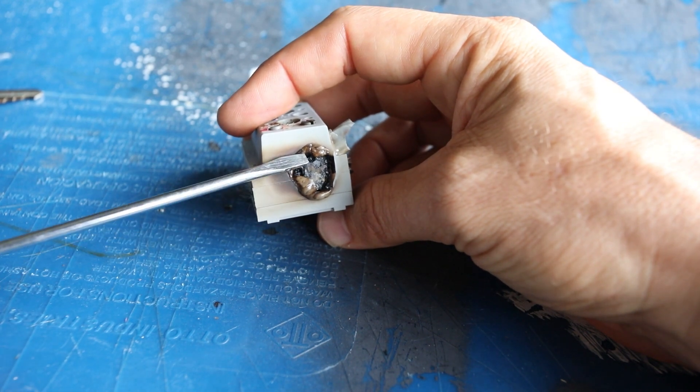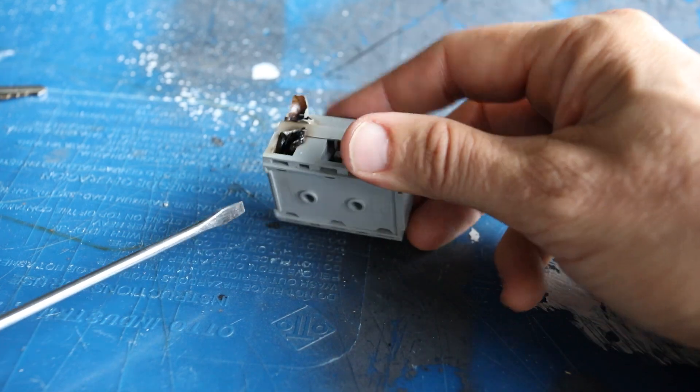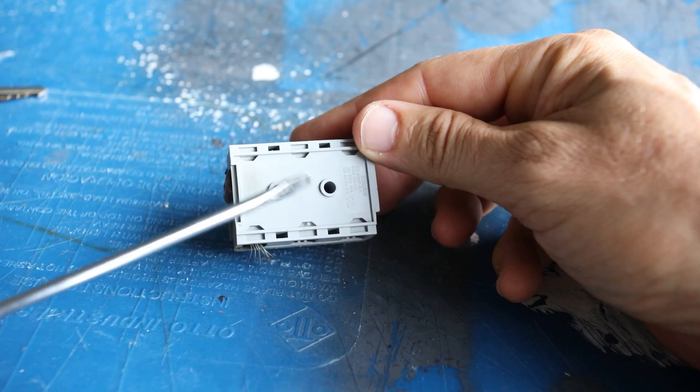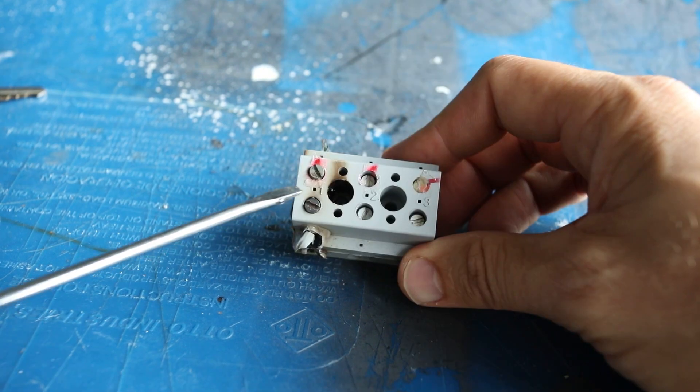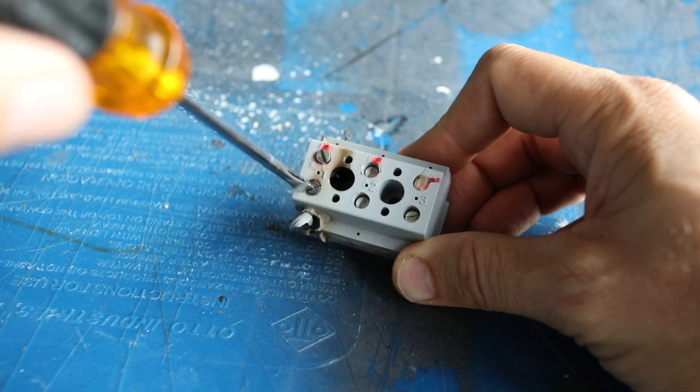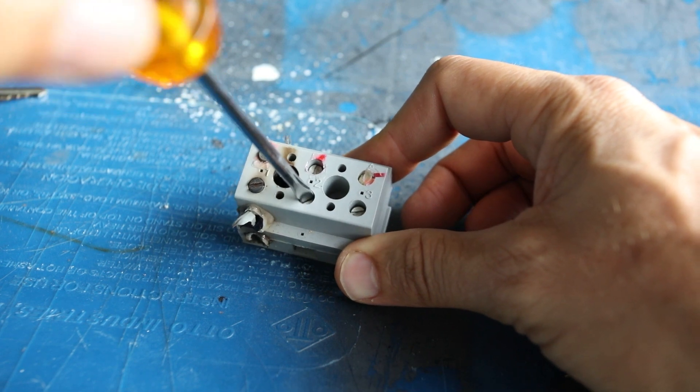It burnt all the way through. That's where the arcing was right there. I looked on the back and sure enough this thing said it was rated for the heavy gauge wire that I put in there. It just had these little screws. It didn't seem like they were ideal for providing the torque necessary to keep these wires nice and snug, at least over the long term.